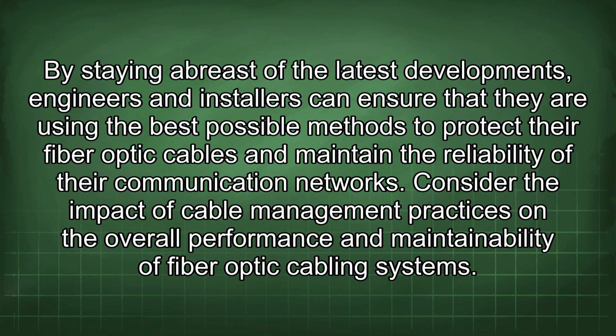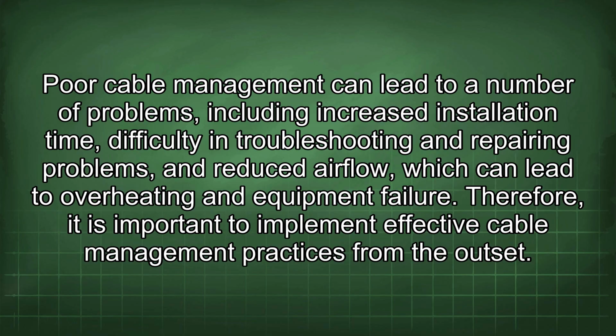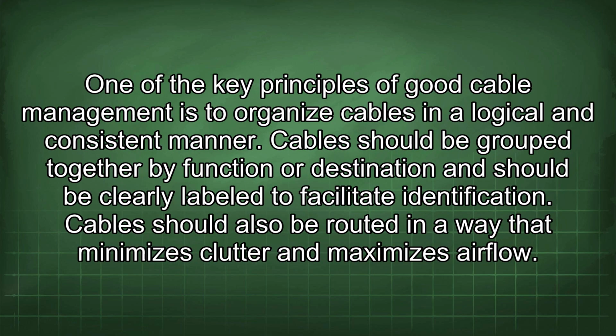Consider the impact of cable management practices on the overall performance and maintainability of fiber optic cabling systems. Poor cable management can lead to a number of problems, including increased installation time, difficulty in troubleshooting and repairing problems, and reduced airflow, which can lead to overheating and equipment failure. Therefore, it is important to implement effective cable management practices from the outset. One of the key principles of good cable management is to organize cables in a logical and consistent manner. Cables should be grouped together by function or destination and should be clearly labeled to facilitate identification. Cables should also be routed in a way that minimizes clutter and maximizes airflow.